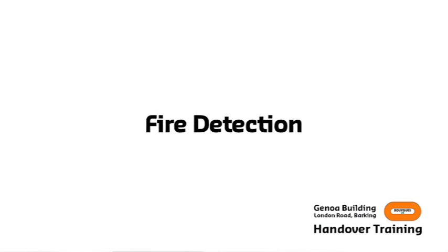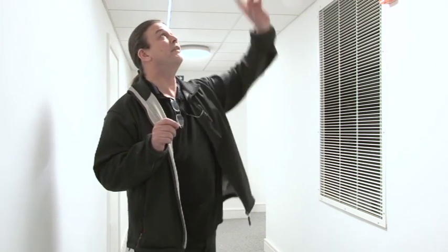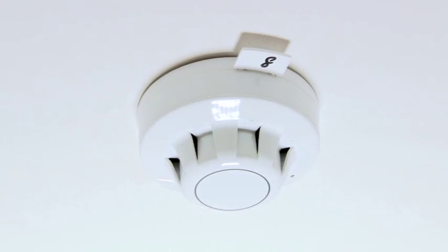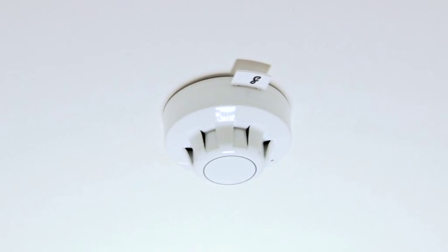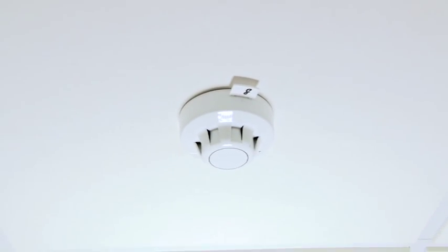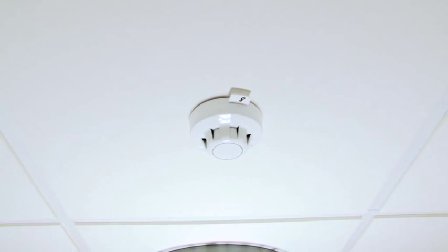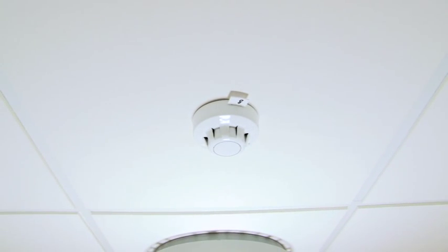The fire detection system within the building, not including the flats, falls into two types of system. We've got the system within the circulation areas and the system within the car park areas. The car park is an entity all of its own, and we should really talk about that separately. But within the residential demise, we have a number of these devices. They're smoke detectors. They will detect smoke when it reaches a particular level, and they will activate the fire alarm system.